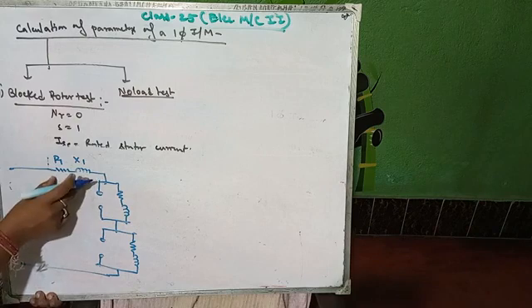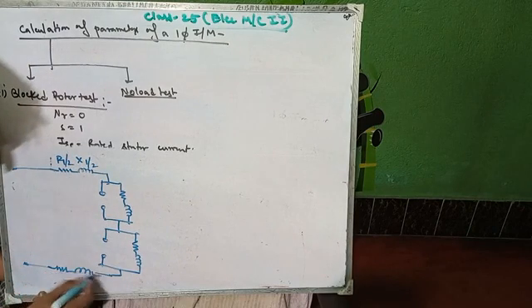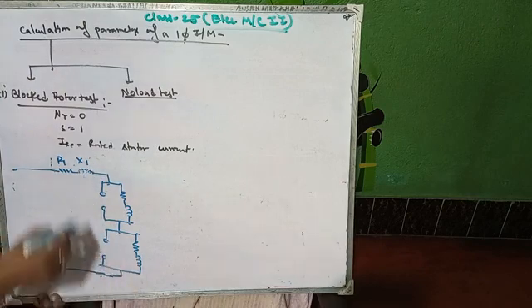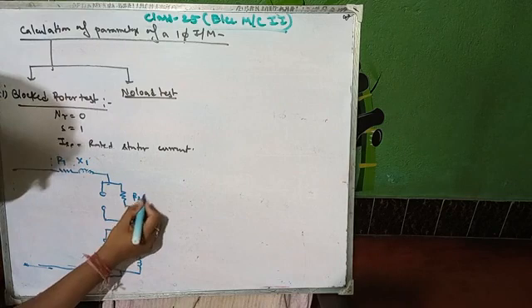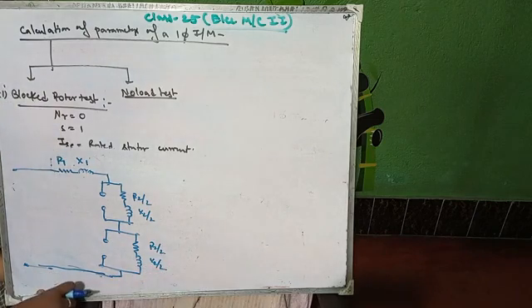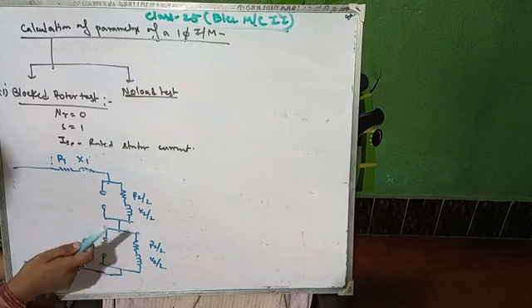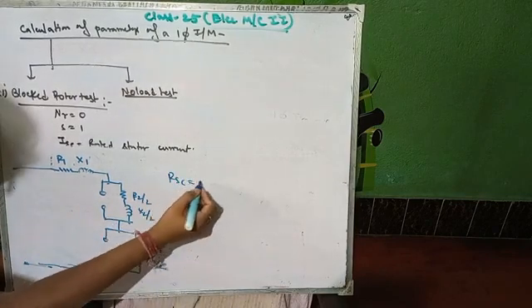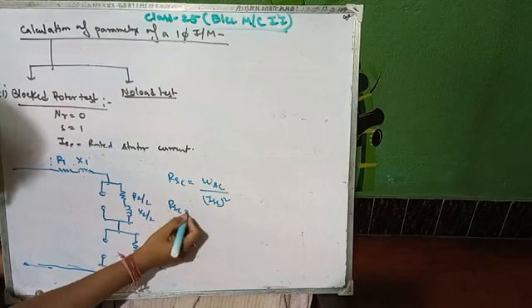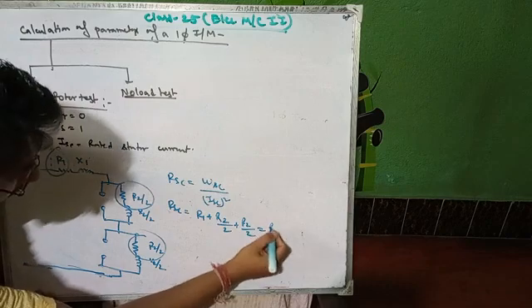The equivalent circuit for the blocked rotor test contains R1, R2/2 and R2/2 (which sum to R1 + R2), and reactances X1, X2/2, X2/2. From this, R_sc equals W_sc divided by I_sc squared, and R_sc equals R1 plus R2. So R2 can be calculated as R_sc minus R1.